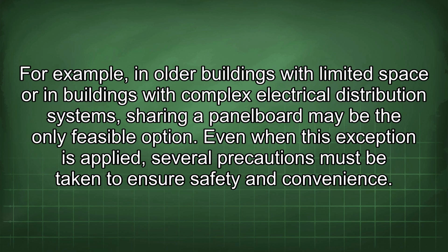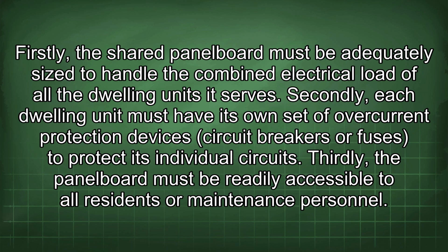Even when this exception is applied, several precautions must be taken to ensure safety and convenience. Firstly, the shared panel board must be adequately sized to handle the combined electrical load of all the dwelling units it serves. Secondly, each dwelling unit must have its own set of overcurrent protection devices, circuit breakers or fuses, to protect its individual circuits. Thirdly, the panel board must be readily accessible to all residents or maintenance personnel.